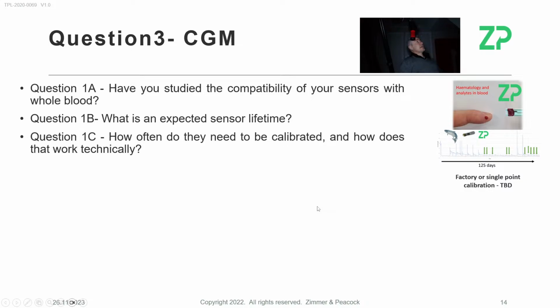In those days, CGMs used to do a finger stick test when they first started to be used. So they were doing single point calibrations. In fact, they would do glucose testing on the patient for the first few days whilst the sensor essentially settled down. These days, they've gone calibration free because they're much stronger on their manufacturing. So calibration is to be determined.